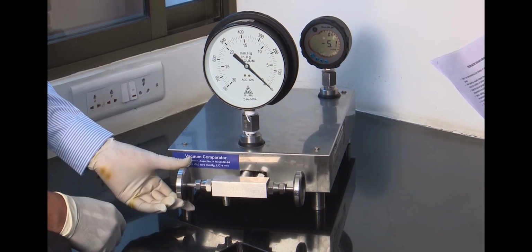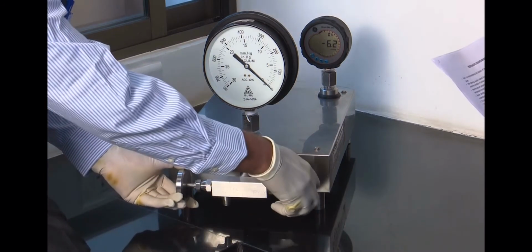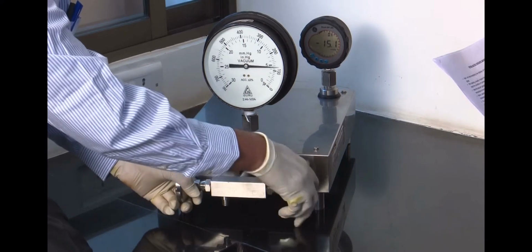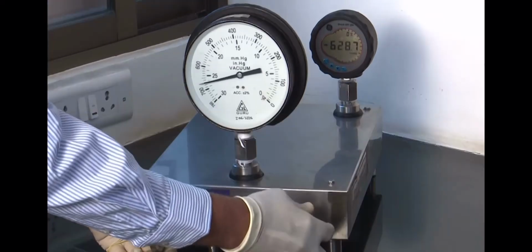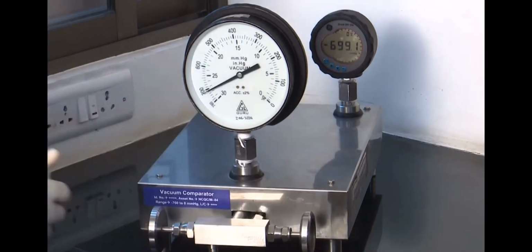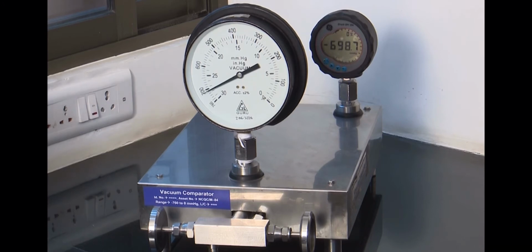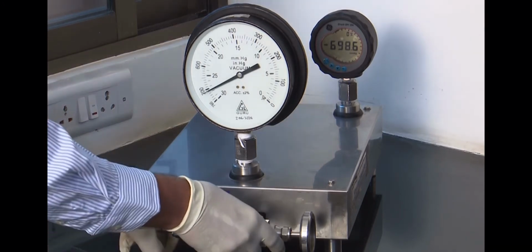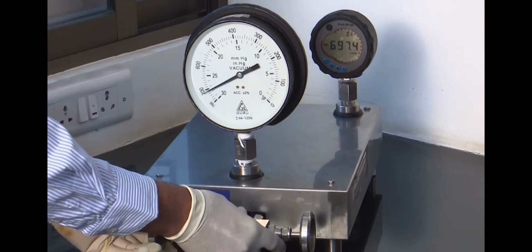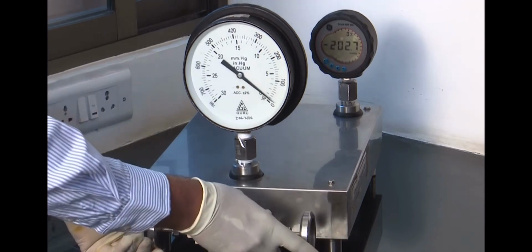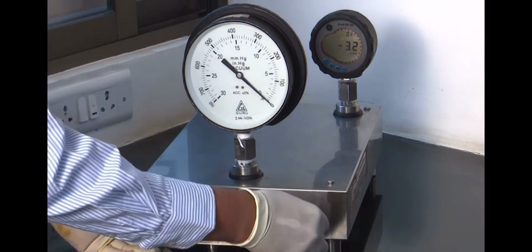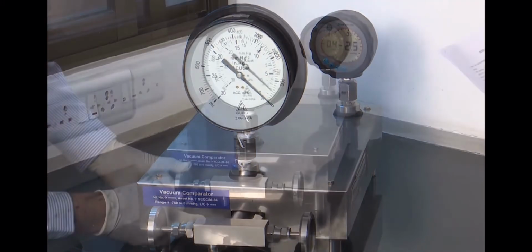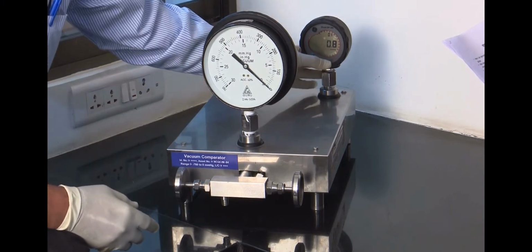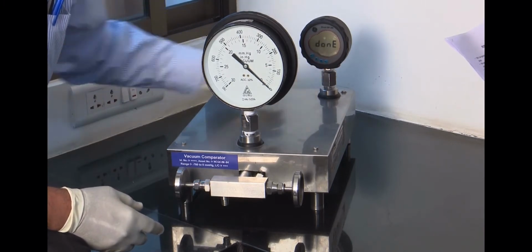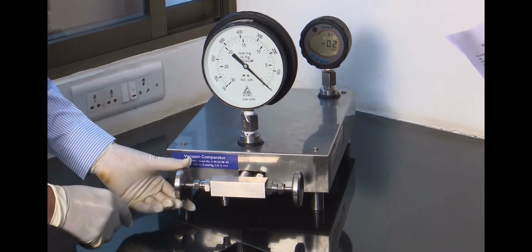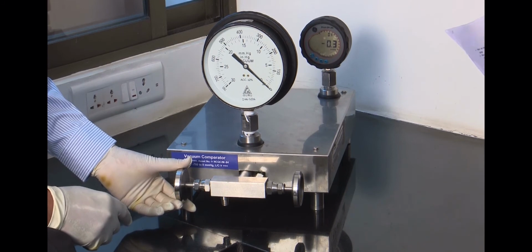Now I am performing preloading. For this I am applying negative pressure up to full range and then I will hold it for 30 seconds. Now I am releasing pressure up to 0 mm Hg. In the same way, we repeat preloading for 2 times. It means preloading is done thrice. After preloading, we are proceeding for calibration.